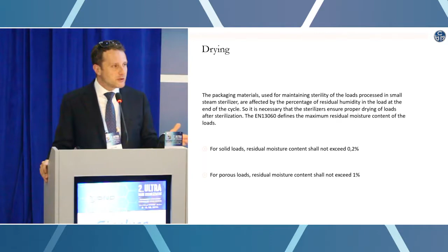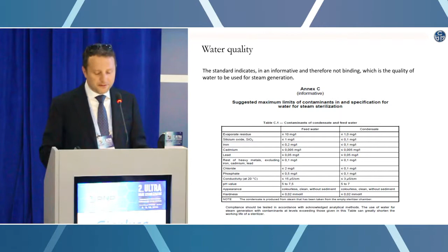Water quality is of paramount importance even for the small benchtop sterilizer. Of course, you cannot use normal tap water or aquarium water, as I've already seen on the market, but you have to use at least demineralized water. First, because otherwise you will destroy the machine and spend a lot of money to buy a new one. But second, you will also destroy your surgical instruments, because the minerals contained in the water and sprayed by the steam will affect any type of stainless steel surgical instruments inside the sterilizer. You will have blue spots, yellow spots, rust, and jeopardizing stains, so you'll have a lot of different problems.